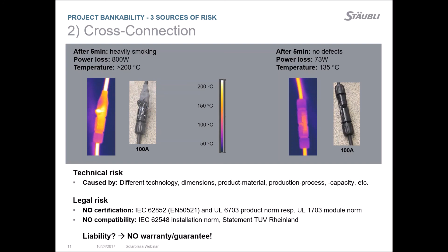Last but not least, the third source of risk is correct installation of the whole cabling. Here we have to focus on the so-called crimping, which is the connection of the connector with the cable. For correct crimping, a certified crimping tool must be used, suited to the particular type of connector. Usually the installer plugs the connectors in the field, so it's crucial to work with a well-experienced, trained EPC or installer, and to use the adequate tool.